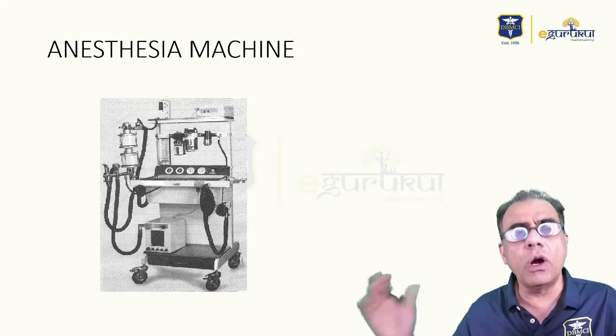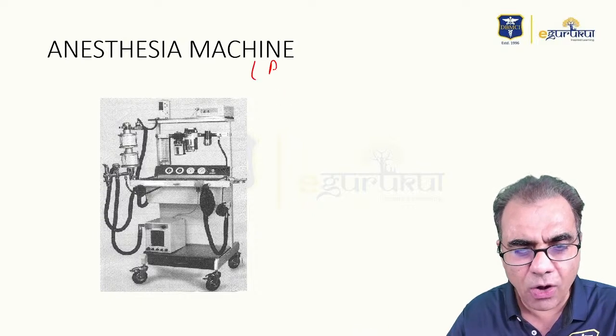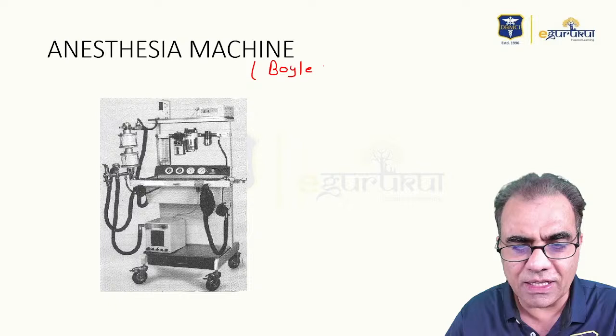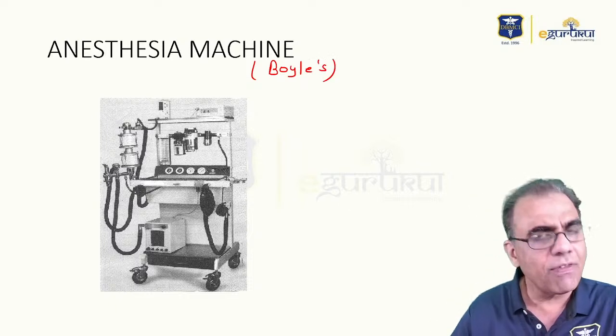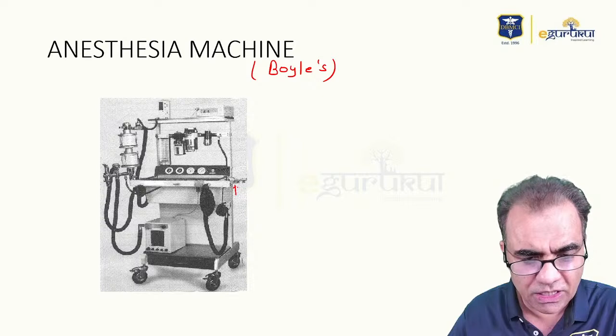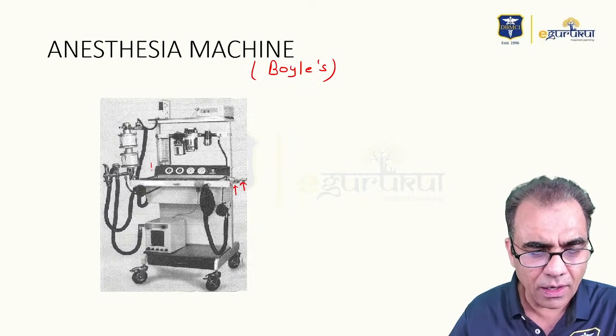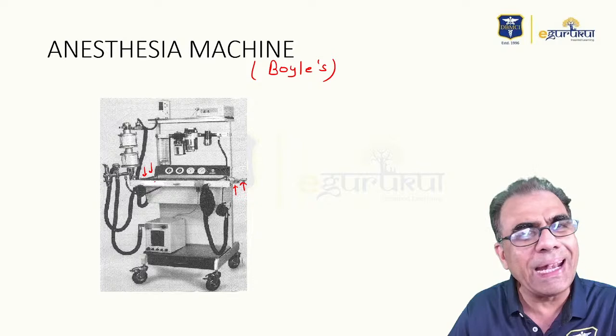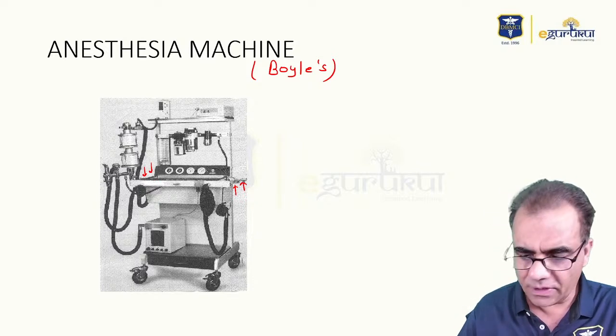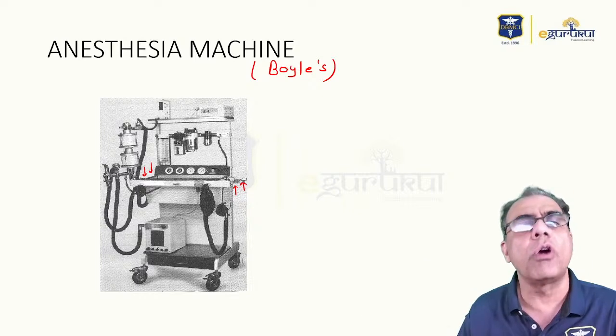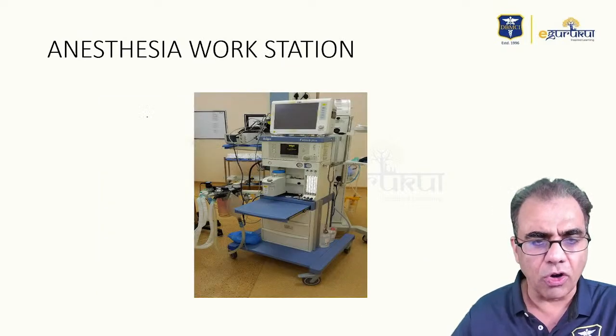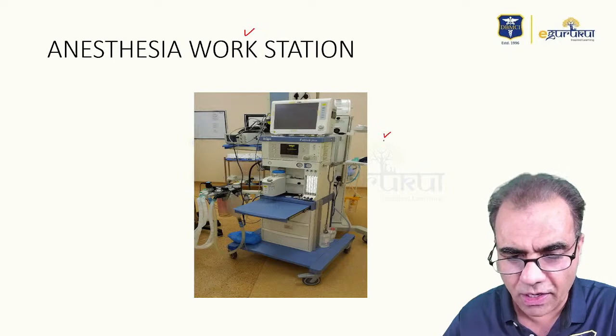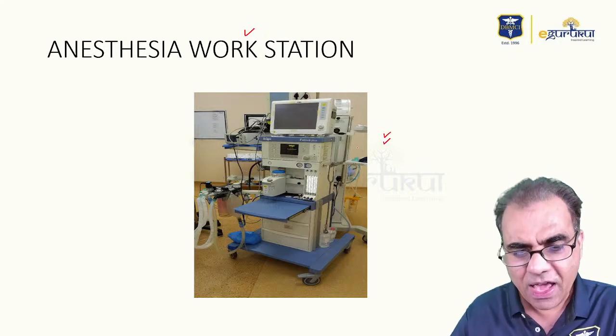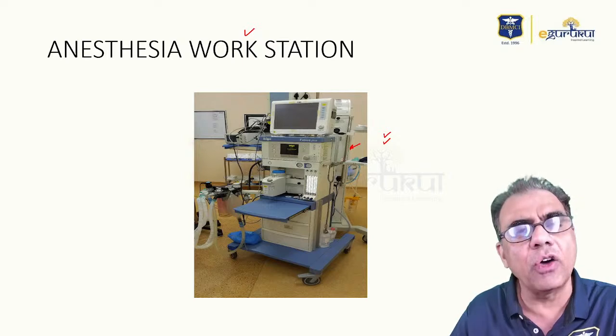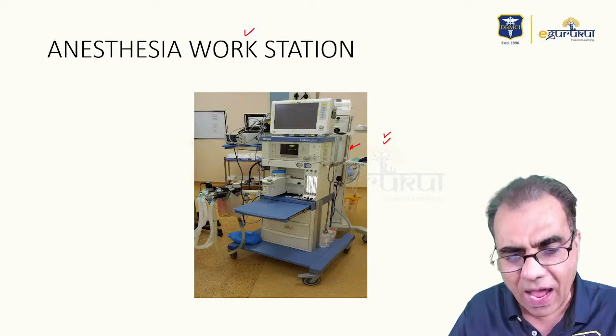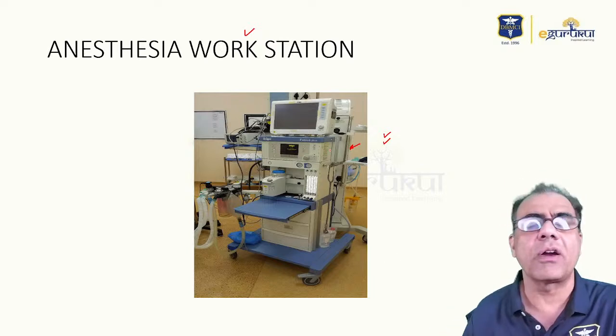Then this is how an older anesthesia machine used to look. In older times we used to call the anesthesia machine Boyle's machine. So this is a very basic Boyle's, and these are the positions where central supply or cylinders will be fitted. So they should have a pin index here. But nowadays, we have modern anesthesia machines which are called anesthesia workstations. A modern day anesthesia machine appears like that, where pins will be at the back of the cylinder, because central supply and cylinders are attached at the back of the machine.